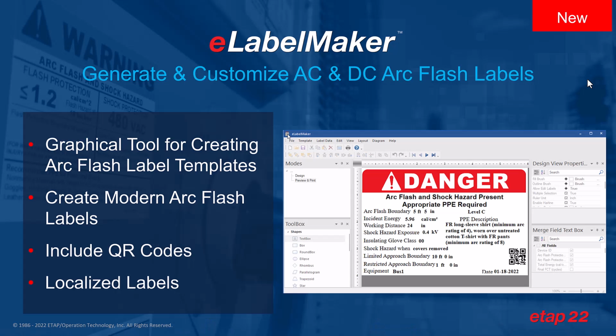However, this is a case where the trees are with a height greater than a structure height. If there are no other objects around this particular structure, such as trees, the risk evaluation is automatically adjusted, and it is now recommended that a lightning protection system be installed. So this is a very quick example of the lightning risk assessment calculator, which you can see in a subsequent webinar in more detail. ArcFlash also includes a new capability, which is Label Maker.